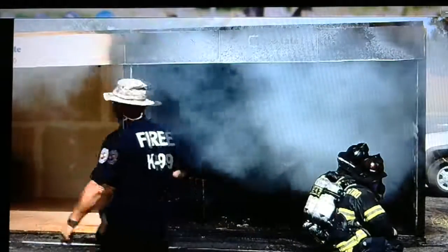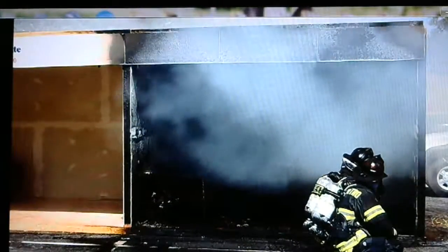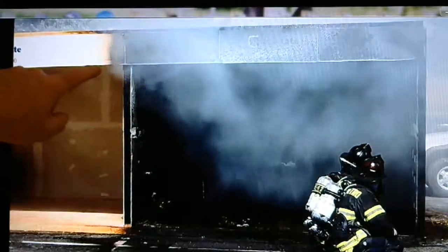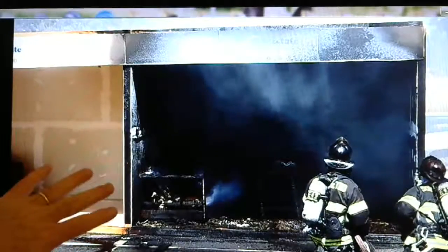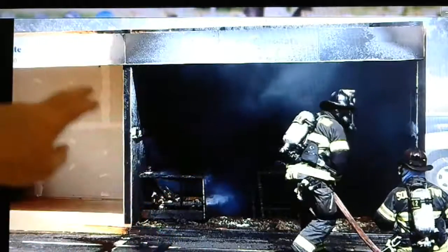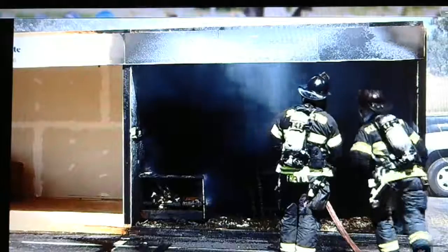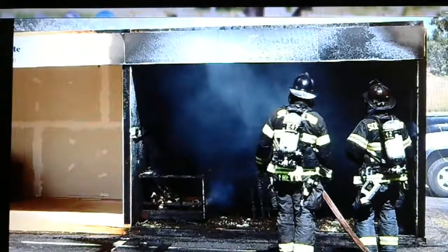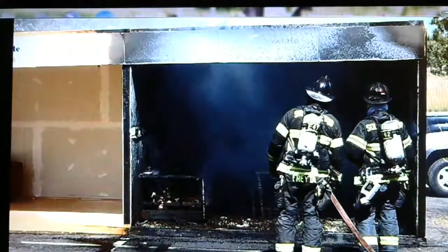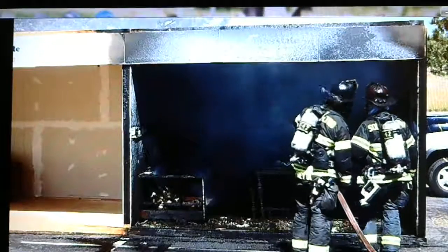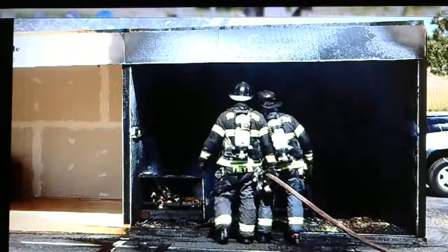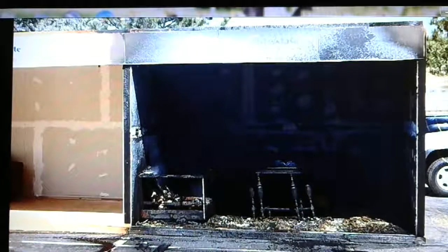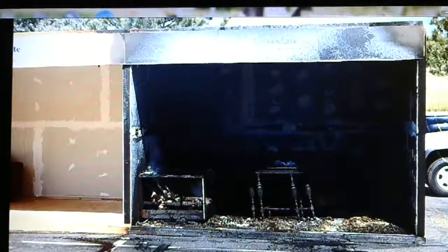Again, these are great for showing people the power of fire. They're great for demonstration. In this case, we have a sprinkler head over here, 2 layers of drywall, one on each side. Did a great job keeping the heat over here, no problem. When we fired that one up, sprinkler head activated, controlled the fire in the wastebasket, no problem. So compare this video with some of the other photographs on the website, and then when you look at the calculations, you'll understand a little bit more.